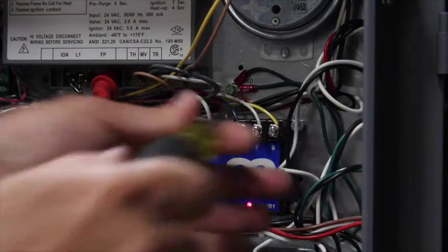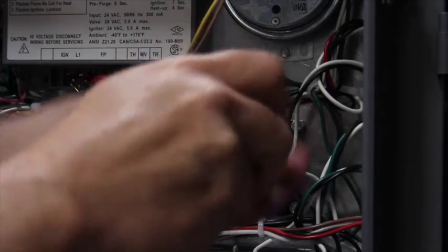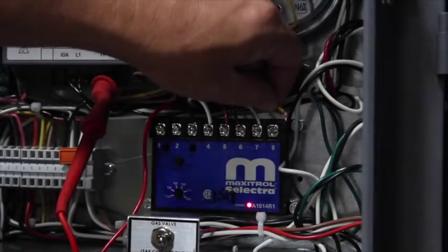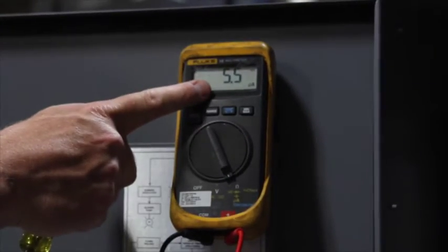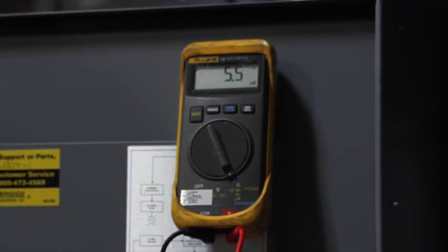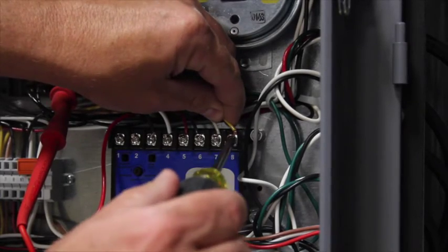Next, remove wire number eight from the amplifier. This will place the heater in low fire. Now verify your flame signal is from three to six microamps. If it is less than three, consult the factory. Next, reconnect wire number eight to the amplifier.